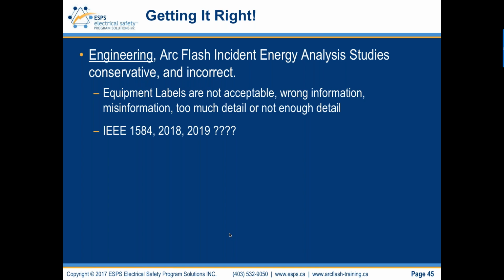Misinformation, too much detail or not enough. They're not compliant to ANSI Z535. The misapplication of the word danger in the signal panel versus warning. IEEE 1584 again, the new formula is coming out later this year. Sorry, not this year, 2018. I hope so. 2019. So again, we'll find out. But the implications to these engineering calculations for incident energy, you need to manage them when IEEE 1584 changes.